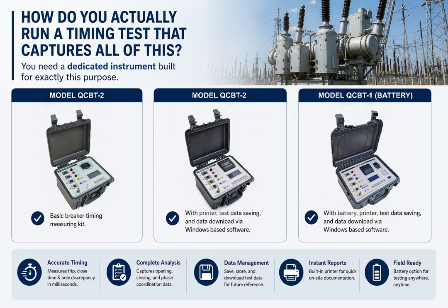So, how do you actually run a timing test that captures all of this? You need a dedicated instrument built for exactly this purpose. This is our circuit breaker timer kit. It is designed specifically to measure everything we just talked about: trip time, close time, and pole discrepancy across all three phases, simultaneously, in a single test sequence.